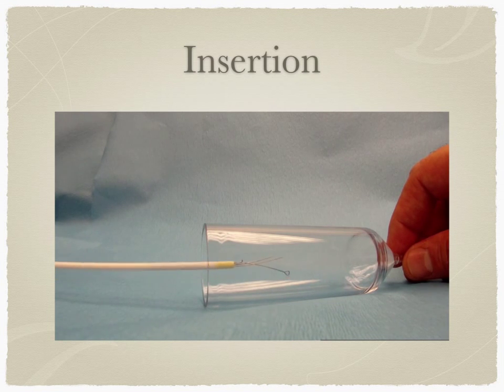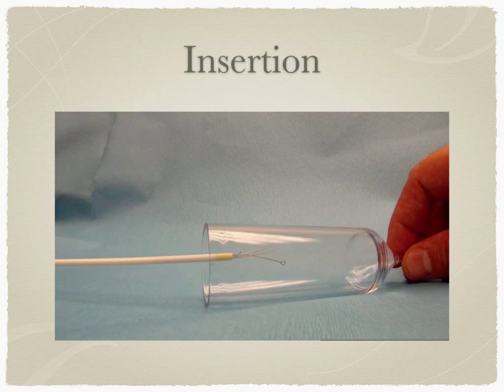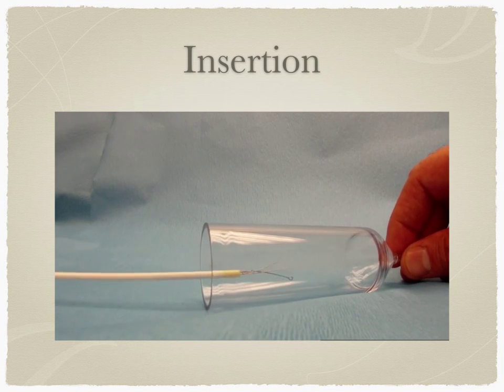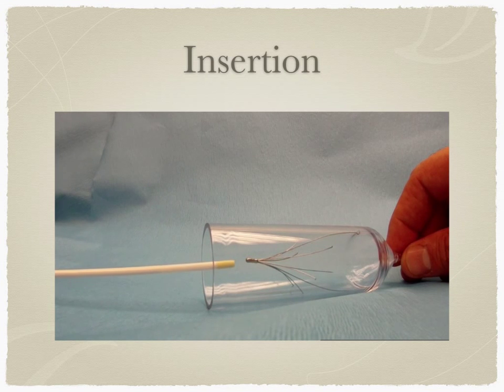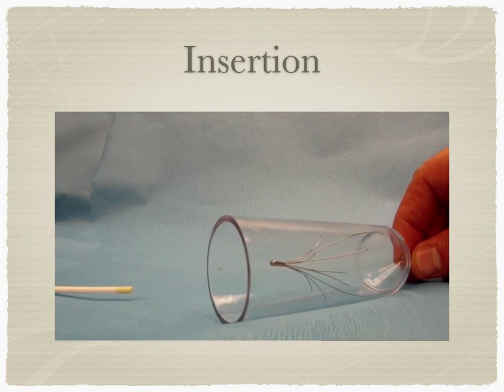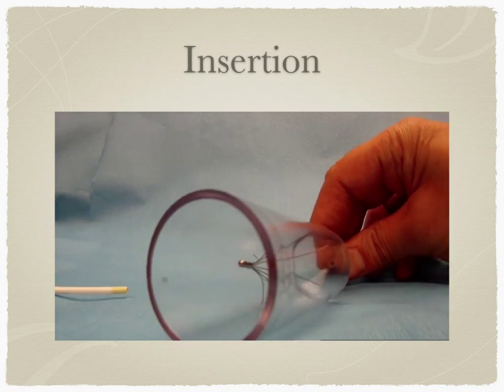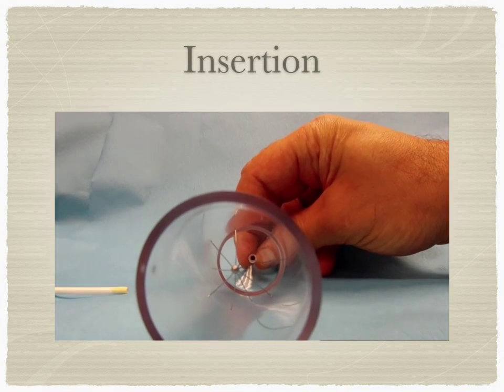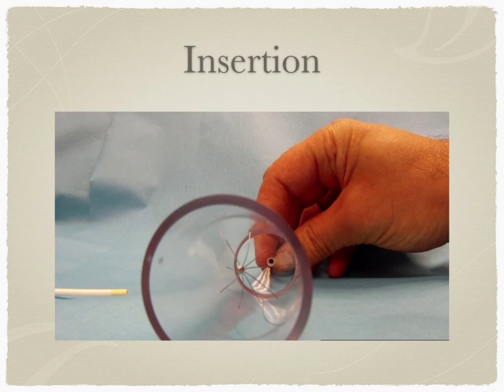This is sort of a more or less spring-loaded environment, as the catheter that contains the filter has a tube inside it. It pushes the filter out. The filter deploys and gets caught within the vena cava, and there are some of those prongs that have sharp edges to them, and they anchor themselves within the wall of the vena cava.